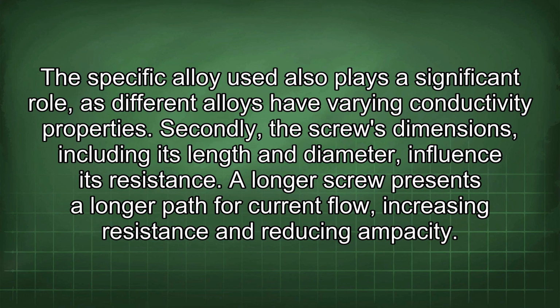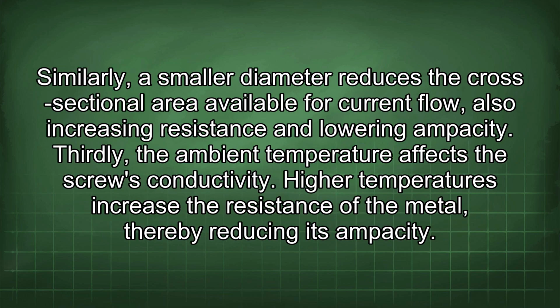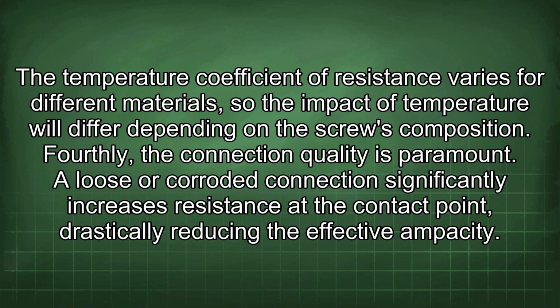Secondly, the screw's dimensions, including its length and diameter, influence its resistance. A longer screw presents a longer path for current flow, increasing resistance and reducing ampacity. Similarly, a smaller diameter reduces the cross-sectional area available for current flow, also increasing resistance and lowering ampacity. Thirdly, the ambient temperature affects the screw's conductivity. Higher temperatures increase the resistance of the metal, thereby reducing its ampacity. The temperature coefficient of resistance varies for different materials, so the impact of temperature will differ depending on the screw's composition.